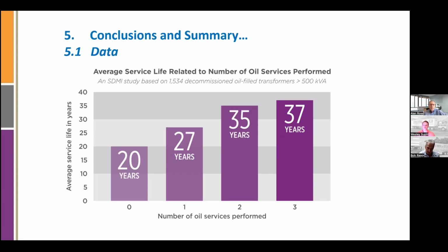The service, from what we data logged here, was moisture reduction and keeping the oxidation inhibitor at therapeutic levels, which is in C57.106 as 0.3% in the US and 0.4% in Canada. And then also moisture reduction. Moisture, acid, and inhibitor levels were maintained in the transformers, and on the transformers that had the services performed over their life, we were seeing nearly 40 years of life as compared to 20.